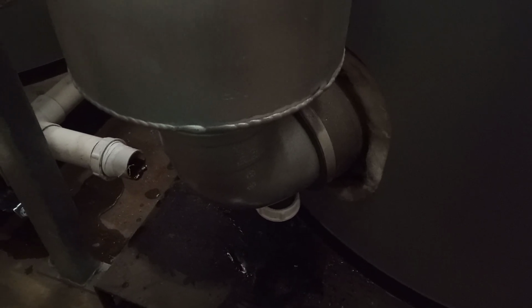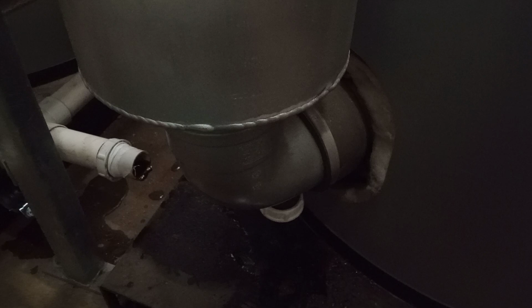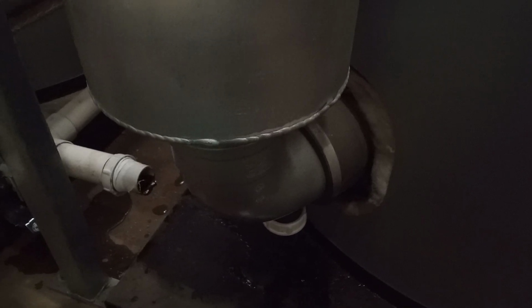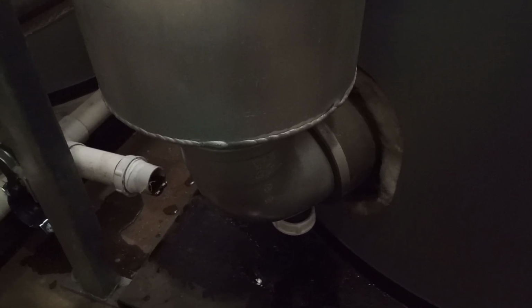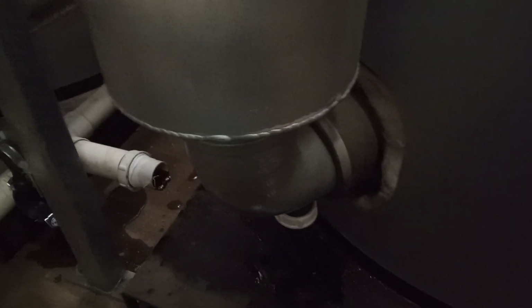But the thing is, they weren't even lighting at all. But yeah, it took an hour for me to go and look at the control panel. So silly me, should have seen it earlier. But nonetheless, I had some fun in it. So always look for the basics first. Go and look for the simplest things, like the knock-off button or the control panel. And so when I did walk in here, before I got my tools out, I should have had a little recce, but obviously my eyes weren't open.